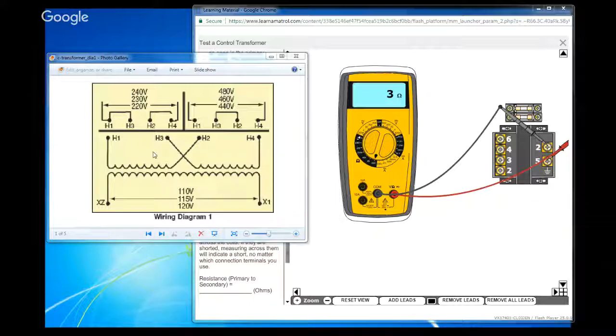So how do I test this? How do I know if this transformer is bad? I don't know what it's supposed to be. Well, most of the time you can generally tell by checking each winding to ground if the transformer is disconnected, but there should be a balance. The winding on this side is exactly the same as this side. So if they're not balanced, they do not have the same ohm reading, then more than likely you have an issue.